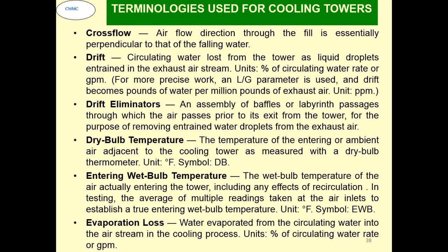Generally, this is something which is there, and many of the industries use drift eliminators, which reduce the effect of losses on account of drift. Because in the drift, what happens, along with the water, the chemicals which are used for the treatment are also taken away, and that means that there is a loss of both water as well as the chemicals which are used for the treatment. If you have a good efficient drift eliminator, you can bring it down to 0.0001% or 0.0005% level, which is an achievable thing as per today in the industry.